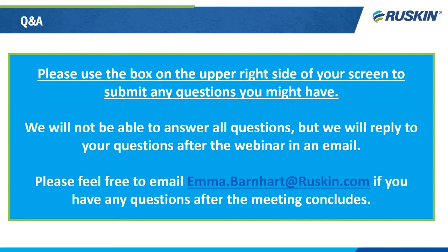Right, thanks, James. So our next question seems to be about ERVs. So Cody, this might be up your alley. It is: what should we do with our ERVs already in operation? Is it safe to leave them running? Thank you, Tessa. My answer to that question would be a resounding yes. If you have ERVs in your system right now, most likely the rooftops, air handlers, and other equipment in your system are designed with that capacity in mind with that energy recovery ventilator. So if you shut it off, you are probably going to see a large increase in humidity, and your equipment may struggle to keep up. And that is not good for high-risk times like right now.